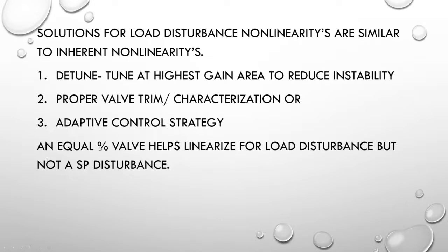An equal percentage valve will help linearize for a load disturbance, but not a set point disturbance. A load disturbance is generally a slower changing disturbance than a set point change, and that's what this speaks to.